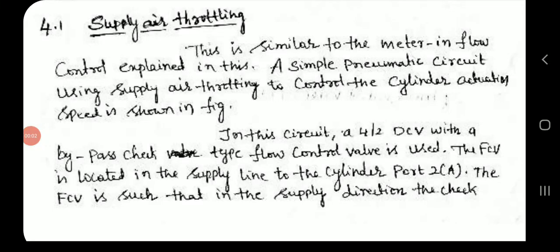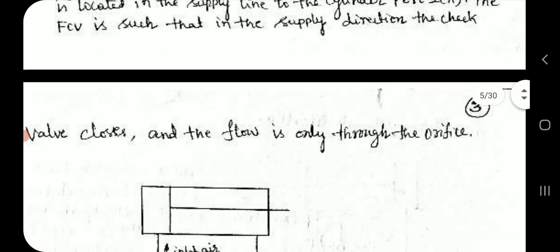Supply air throttling is similar to the meter-in flow control. A simple pneumatic circuit using supply air throttling to control the cylinder actuation speed is shown in the figure. In this circuit, a 4/2 direction control valve with a bypass check type flow control valve is used. The flow control valve is located in the supply line to the cylinder port.